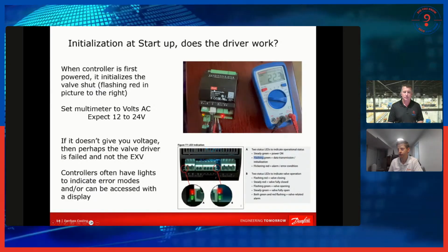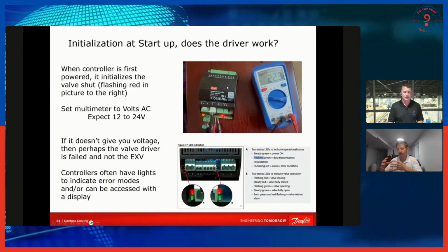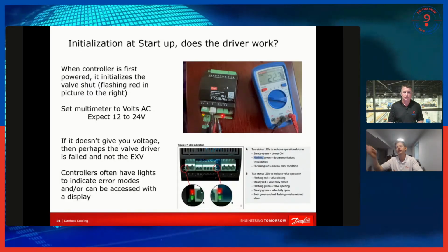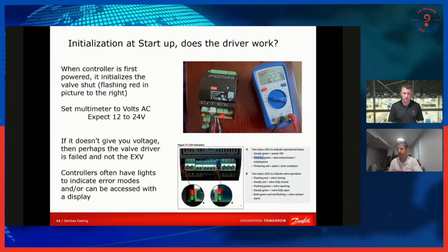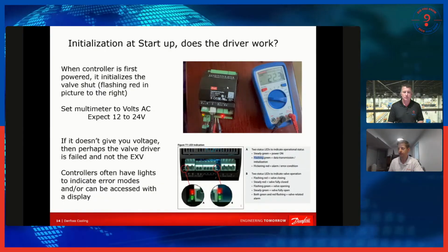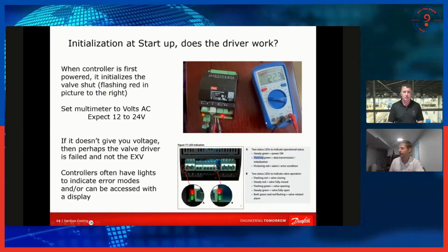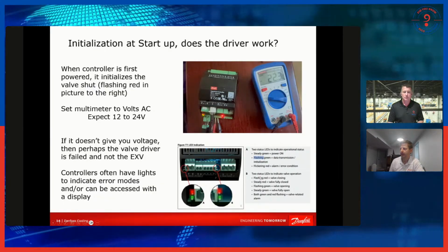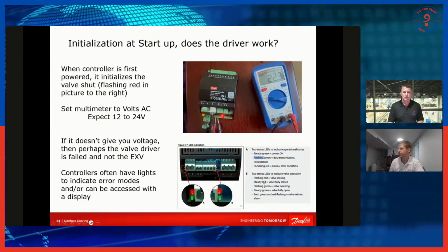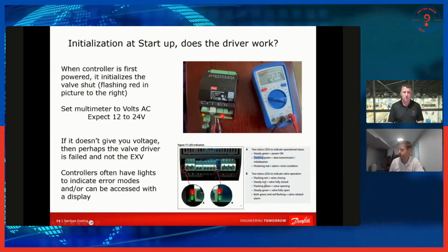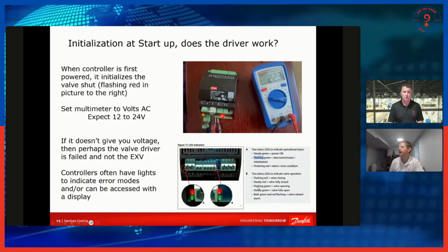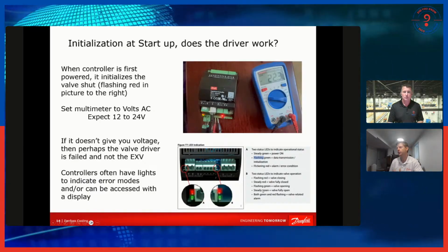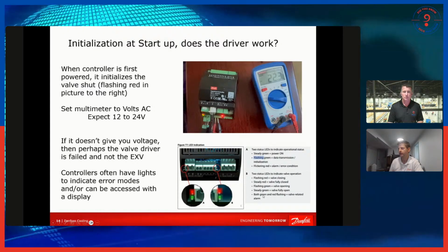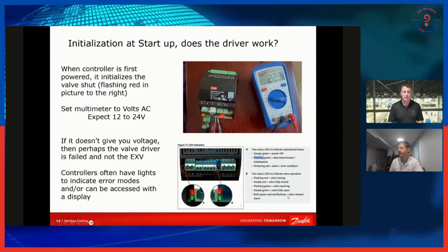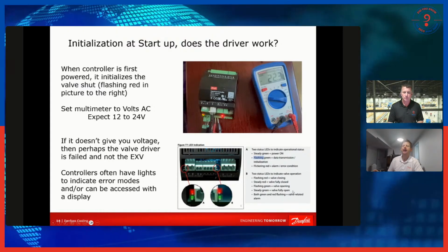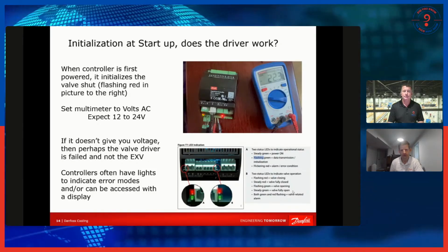Here's a Danfoss controller that we make that doesn't have a display built into it. It can communicate out via Modbus, so it might be on the system controller's display, but on our unit there's not a display itself. We do have little flashing lights indicating when the valve's closing. When the valve is fully closed, it stays steady red. We flash green while it's opening, and steady green when it's fully open. And we flash both lights at the same time to indicate an alarm, which means the controller knows something's not right.